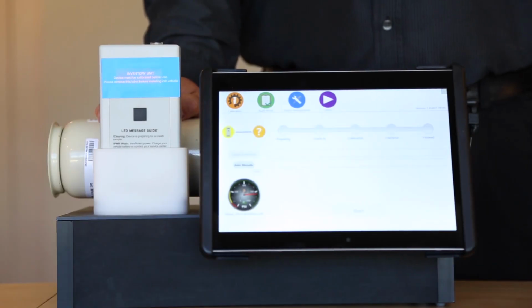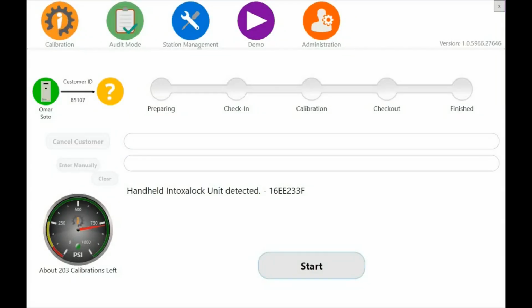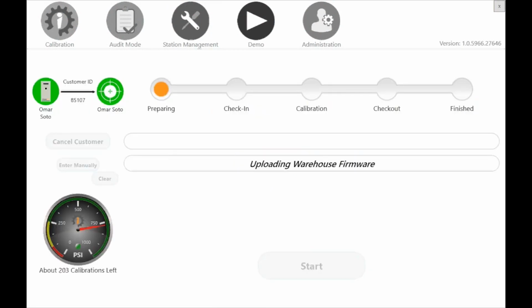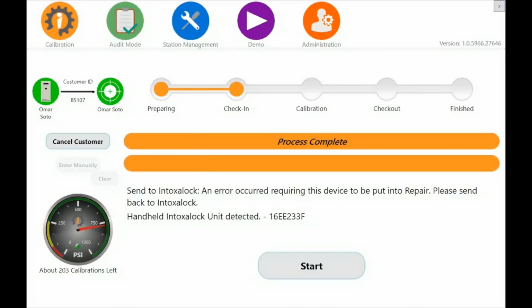For a repair transaction, once you have the handheld inserted and the station connects to the handheld, you will hit the Start button to begin the demonstration. When you begin the repair transaction, you will see the customer's name and customer ID in the left-hand corner. You will hit Start and it will ask you if this is the correct customer. Once you begin, it will look just like a normal calibration, but midway through the calibration, it will flag the customer's unit for repair.